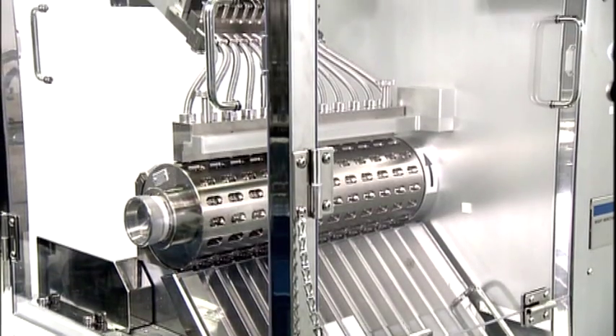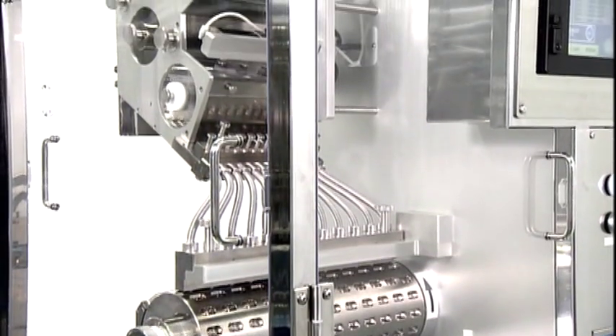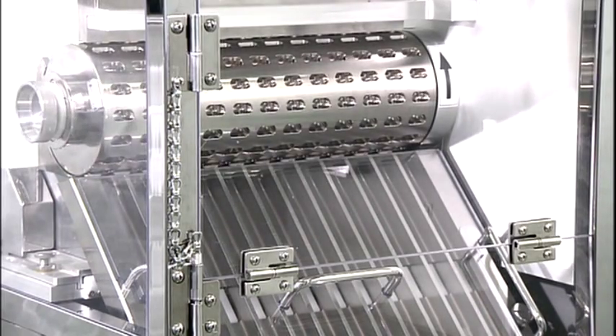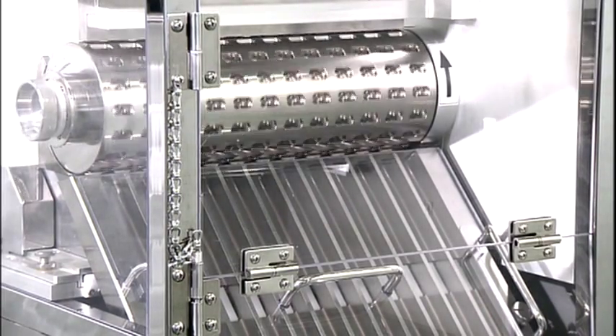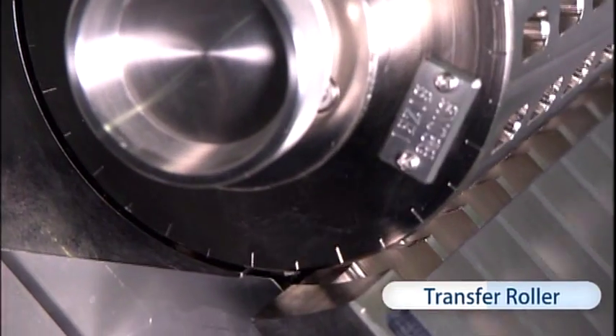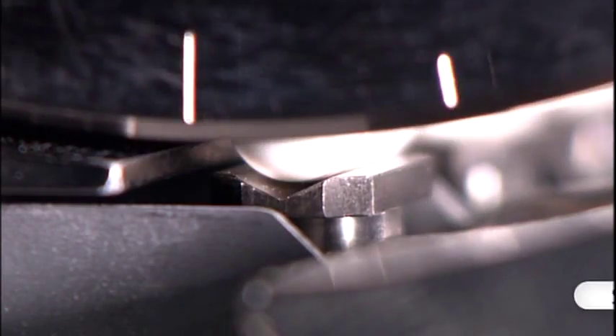Measurement accuracy is affected by vibrations and air currents. An airtight design helps improve cleanliness and prevents external air contamination. The roller rotates 180 degrees and places capsules onto the balance.